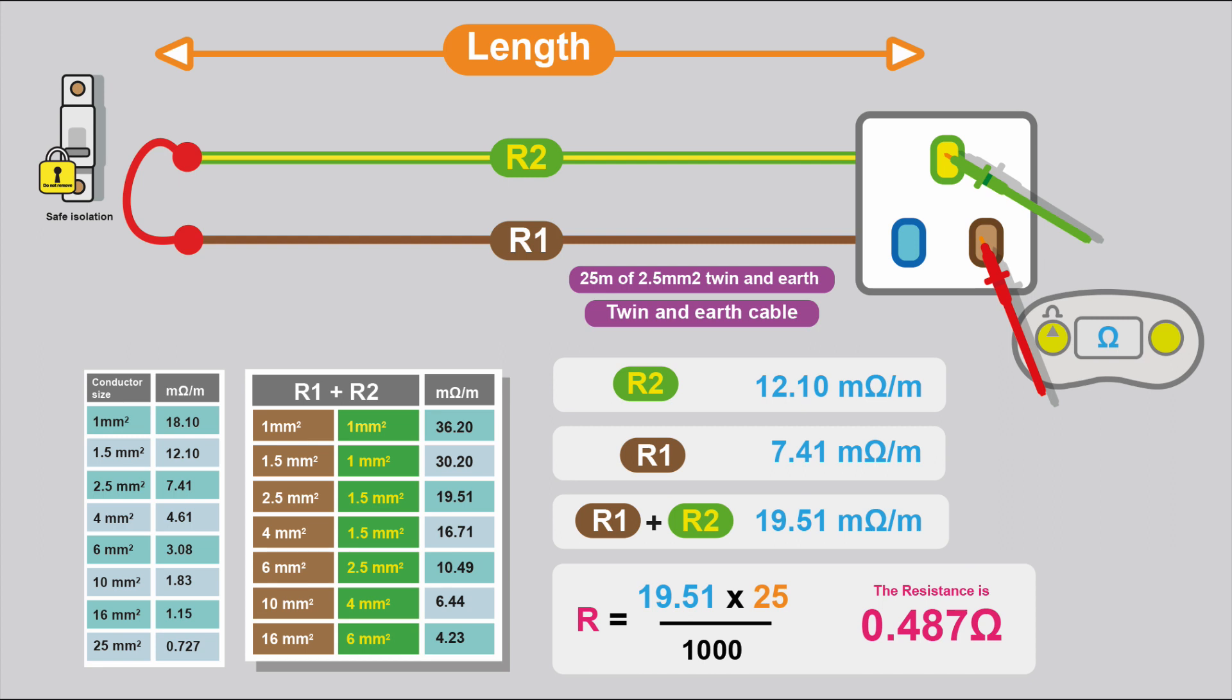In this case, we've installed a socket circuit. We want to do the R1 plus R2 test. It's linked out back at the board. Don't forget, this is all dead testing, initial verification. R1 and R2 is linked out back at the consumer unit. We test at the furthest point. If it's a socket, you could use a socket adapter.